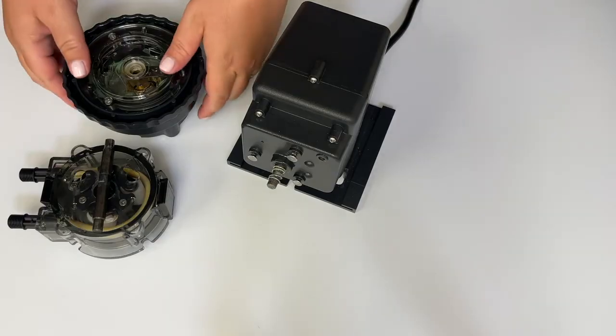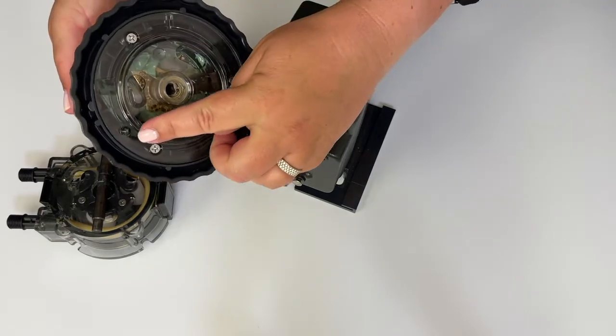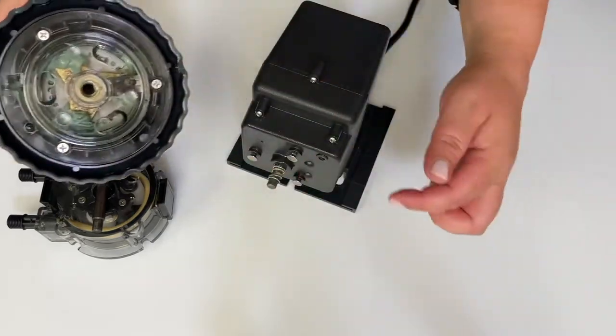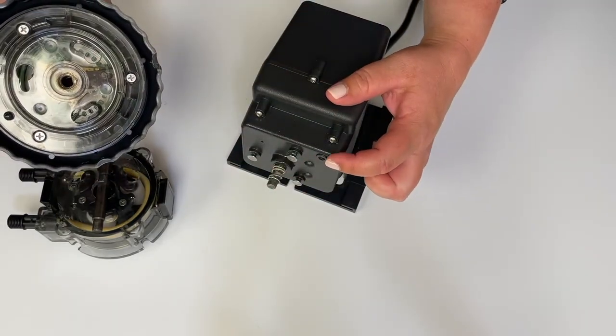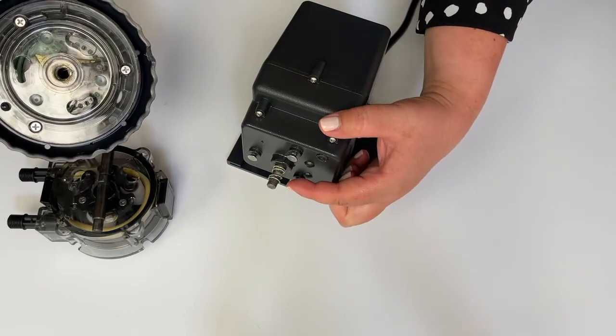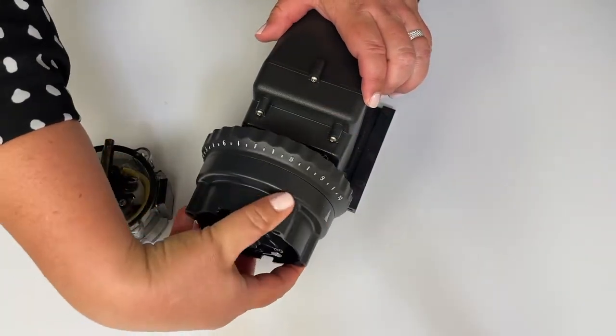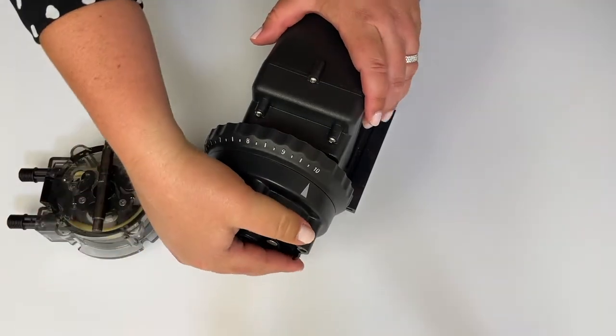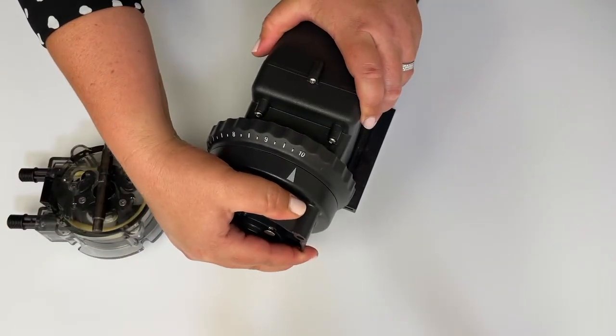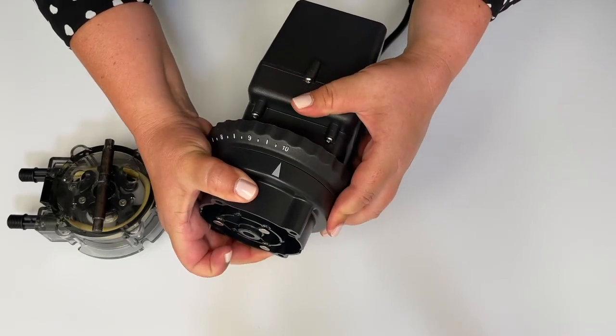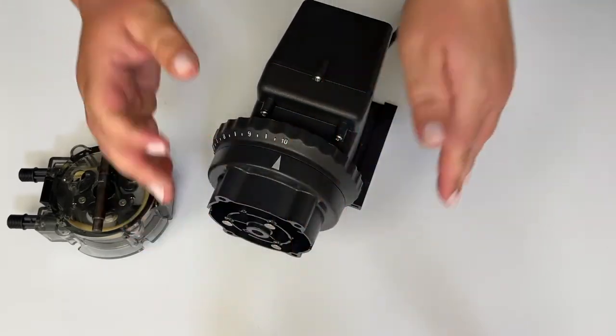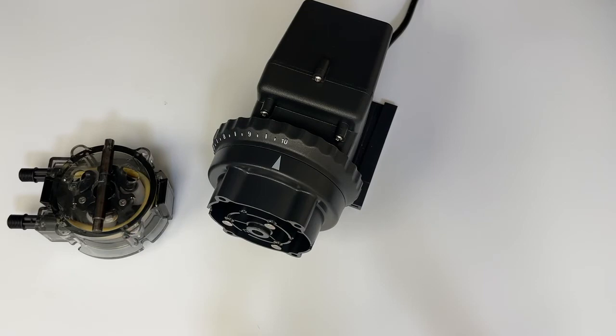To place the feed rate on the pump, first locate the bump on the mounting plate and the small round indent on the motor housing. With the spring in place, position the feed rate onto the motor shaft. Rotate the feed rate to align with the D-shaft. Position the white arrow at 1 o'clock and press the rivets into the holes. Twist counter-clockwise to lock in place.